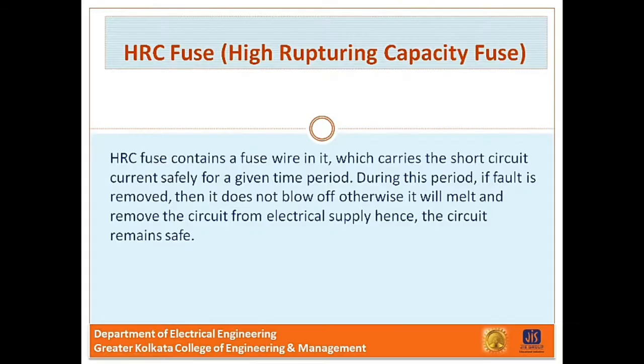So let's start. HRC fuse, high rupturing capacity fuse. Now the primary objection of low and uncertain breaking capacity of semi-enclosed rewirable fuse is overcome in HRC cartridge fuse. Now HRC fuse contains a fuse wire which carries the short circuit current safely for a given time period. During this period, if fault is removed, then it does not blow off, otherwise it will melt and remove the circuit from the electrical supply. Hence the circuit remains safe.